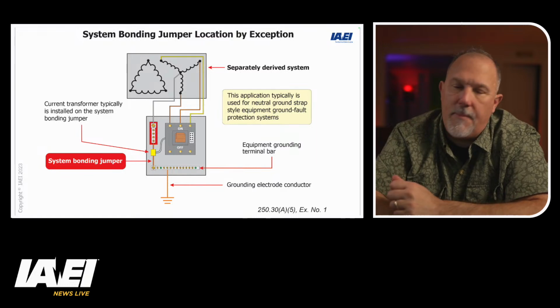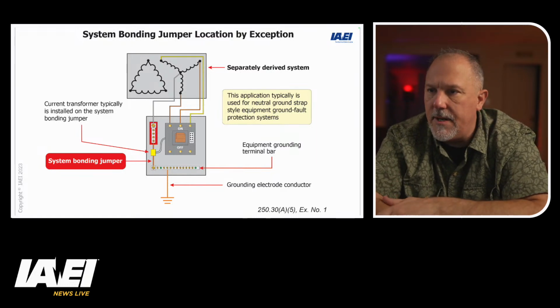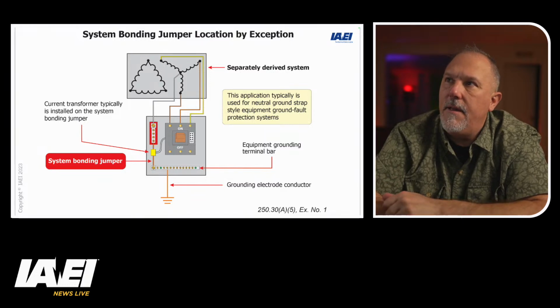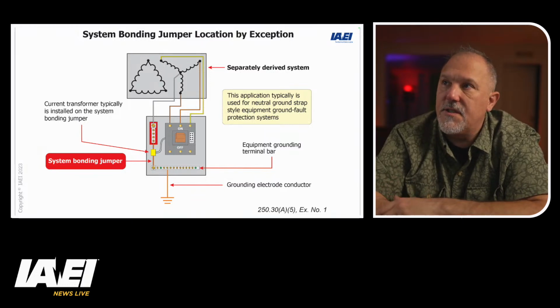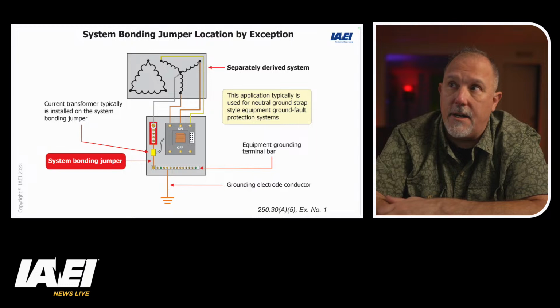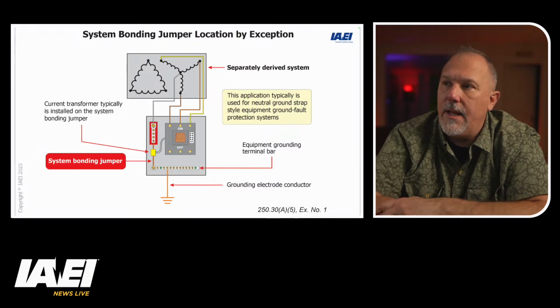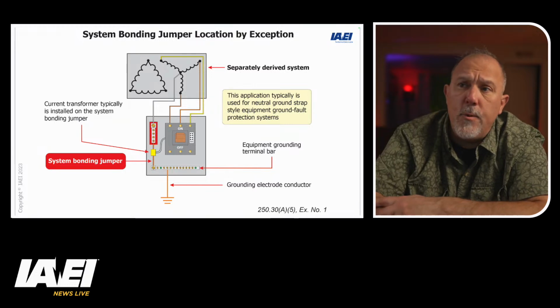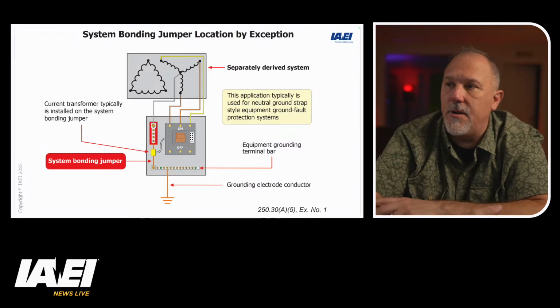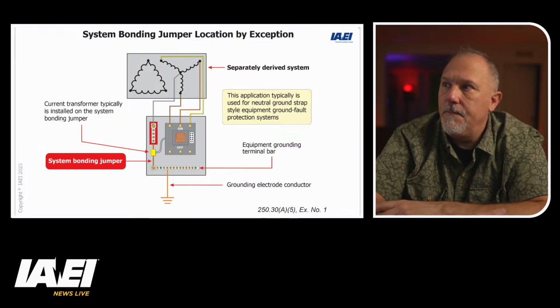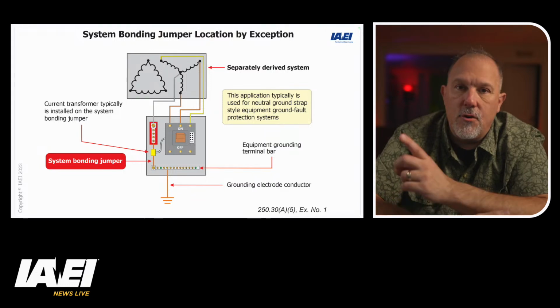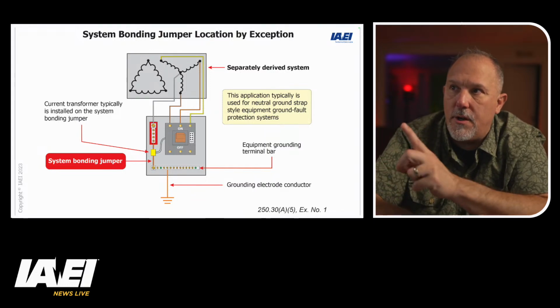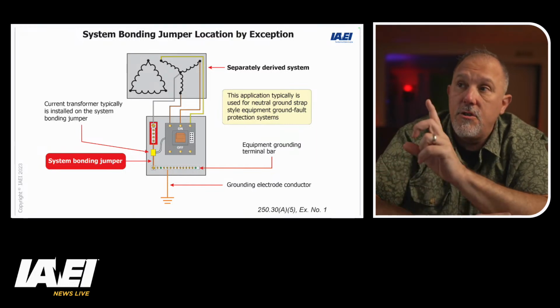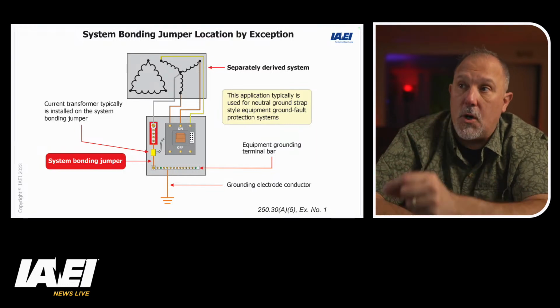I like this image a little bit better. I think David or somebody had pointed out earlier. This image is really nice because you have your separately derived system. There's your grounded conductor, your 3 hot conductors, and we land in a piece of equipment, at which point we have our system bonding jumper. There's your grounding electrode and your grounding electrode conductor. You have your grounding bar, terminal bar, and that's bonded with the grounded terminal bar through the system bonding jumper.